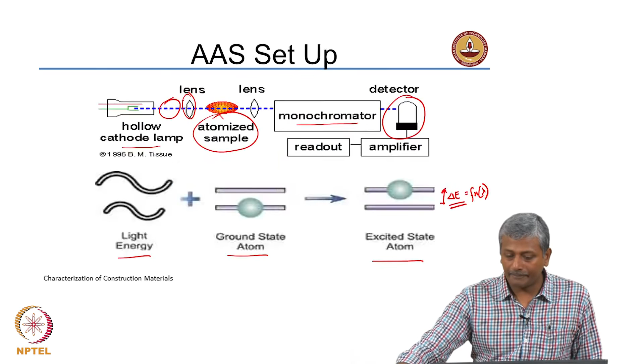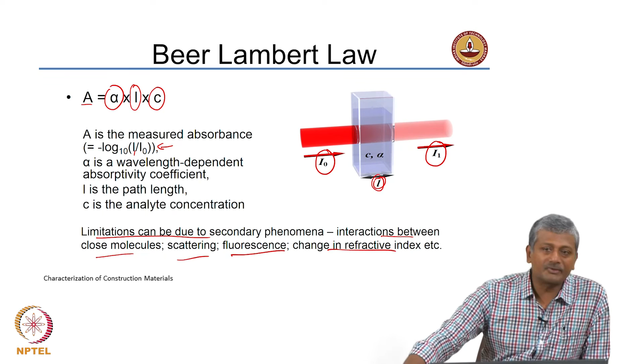What do you mean by that? If you have a liquid filled inside a tube, we know exactly the length through which the light has to pass through, but in a furnace, when the atoms are getting excited to the gaseous state, we do not know if the gaseous atoms or ions are perfectly lined up all along the length of this furnace directly in the path of the beam. So, we do not know that length for sure. Because of that, application of Beer-Lambert law in typical AAS studies is not easy.